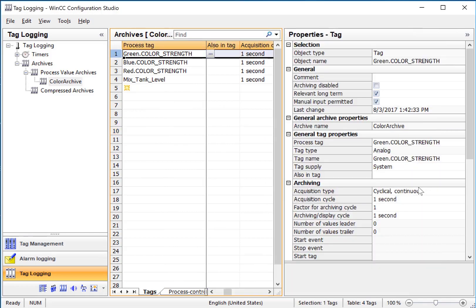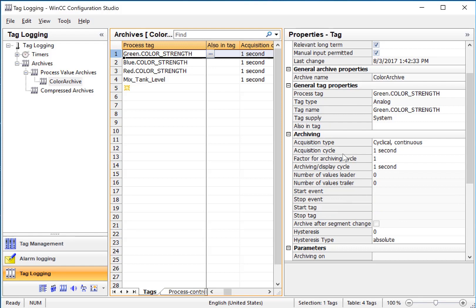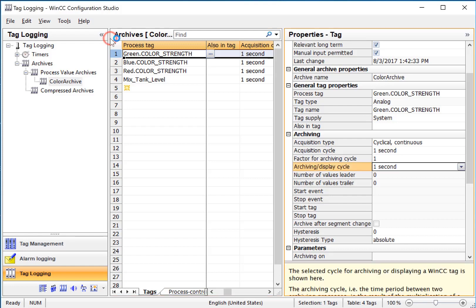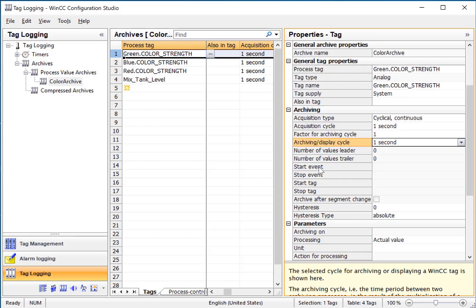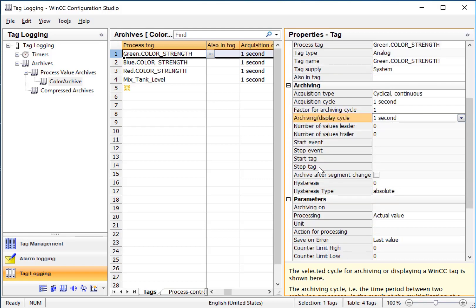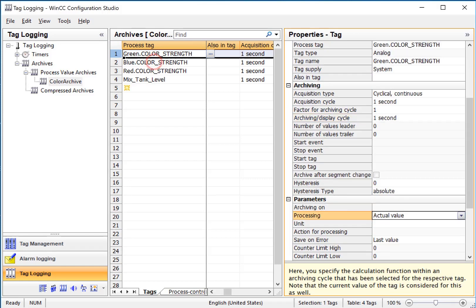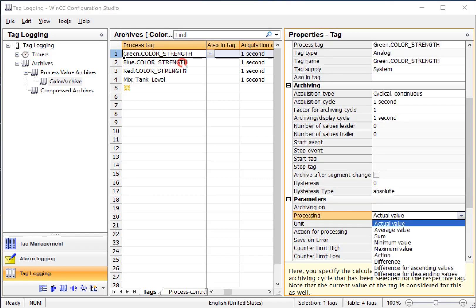If we look at the property section of a given tag, there's some interesting properties in here. The acquisition cycle is how often the tag logging runtime manager acquires the tag value, and the archiving cycle is how often it puts it into the database, and all of these take into account the processing.